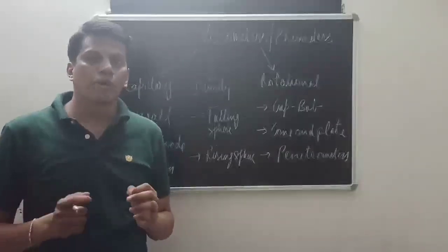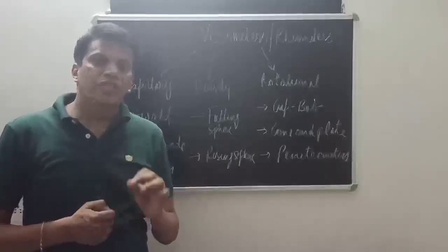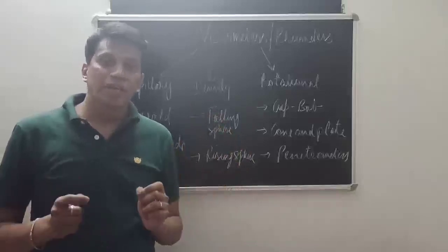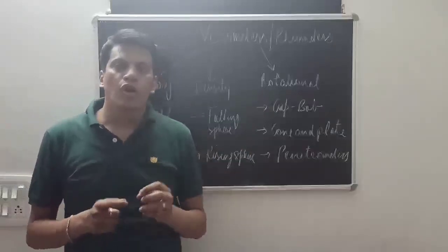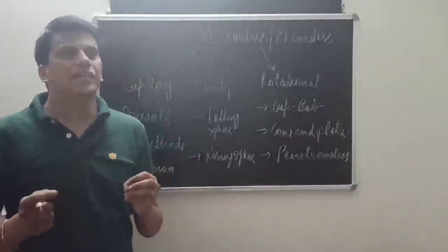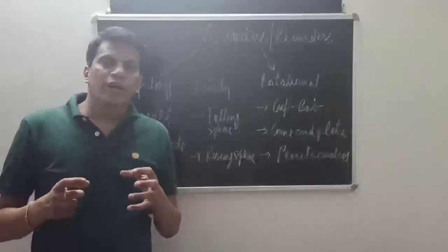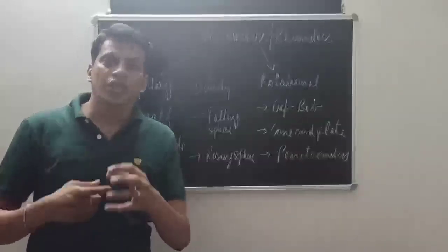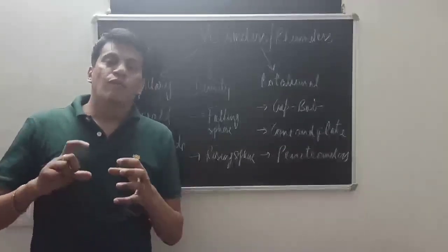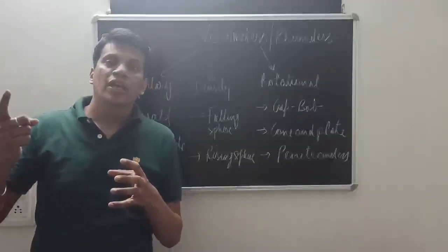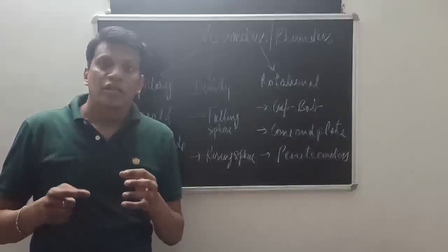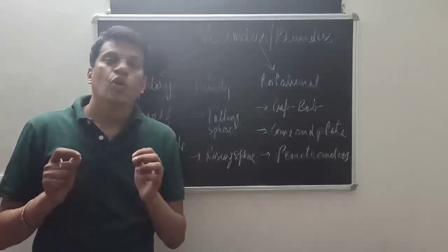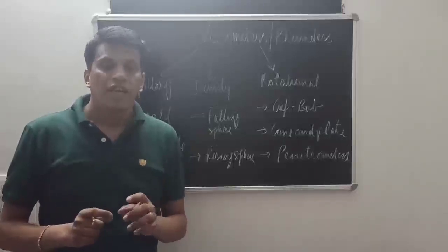One point viscometers are those which determine only a single viscosity value. This means they are only useful for Newtonian material. These instruments do not change the shear. Since there is no change in shear, what is happening to the viscosity is not noticeable. Therefore, they are used only for materials whose viscosity is constant.